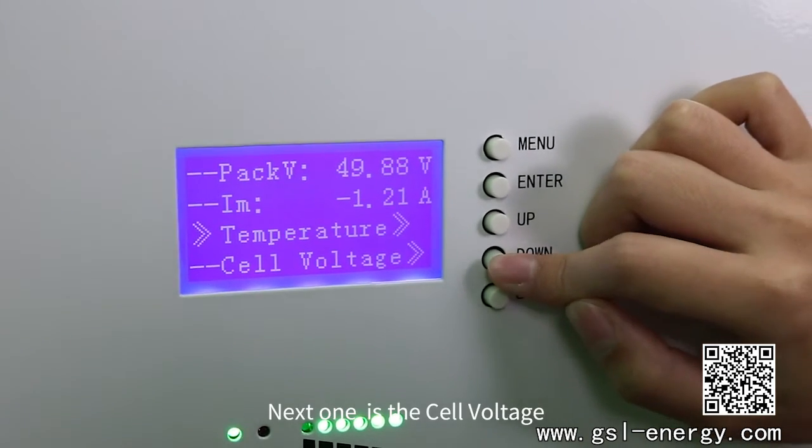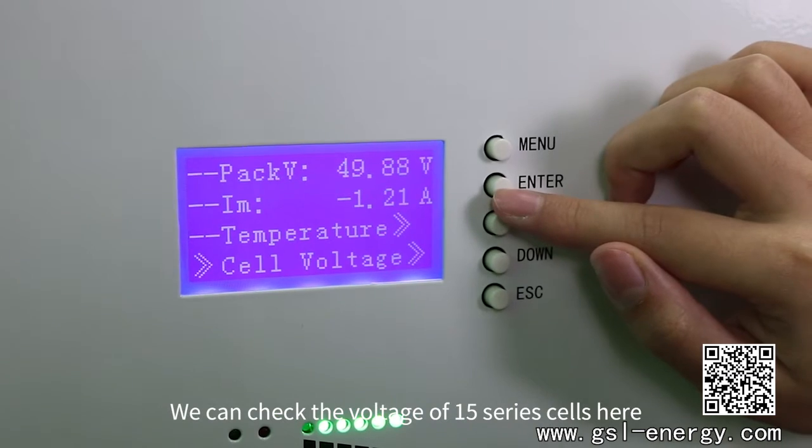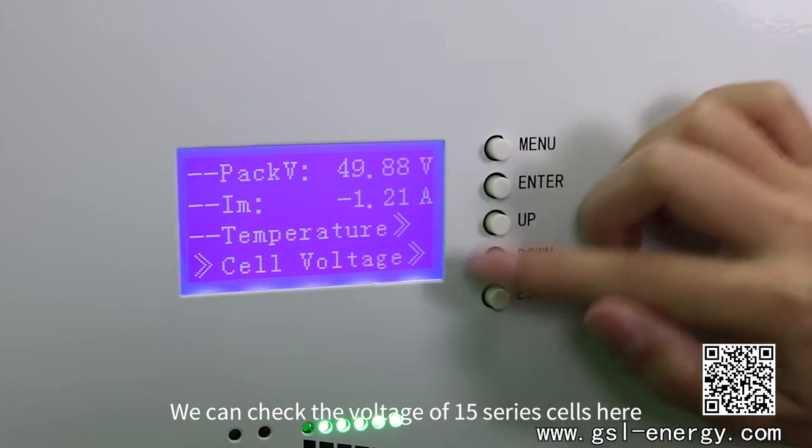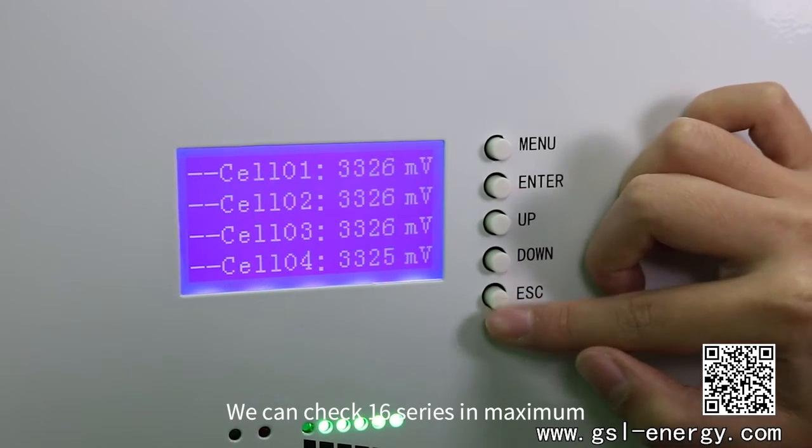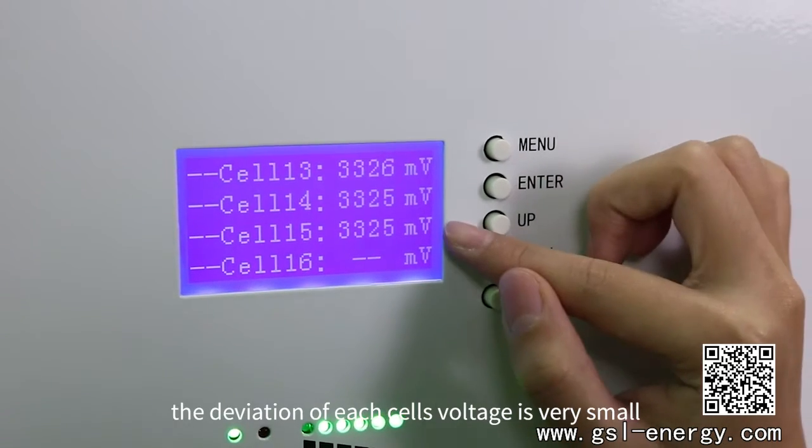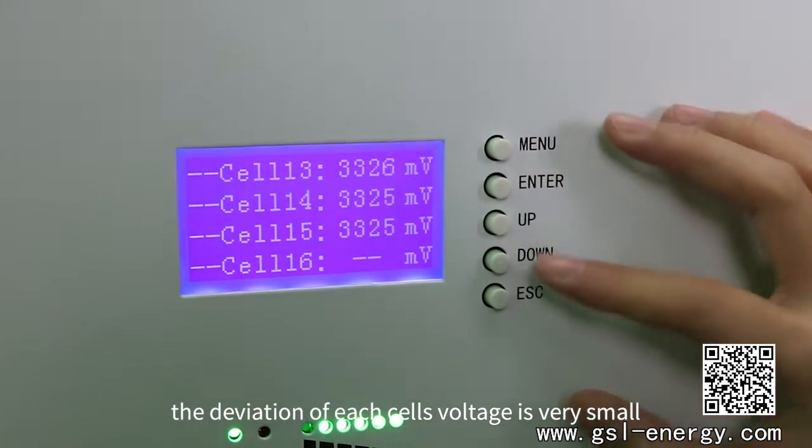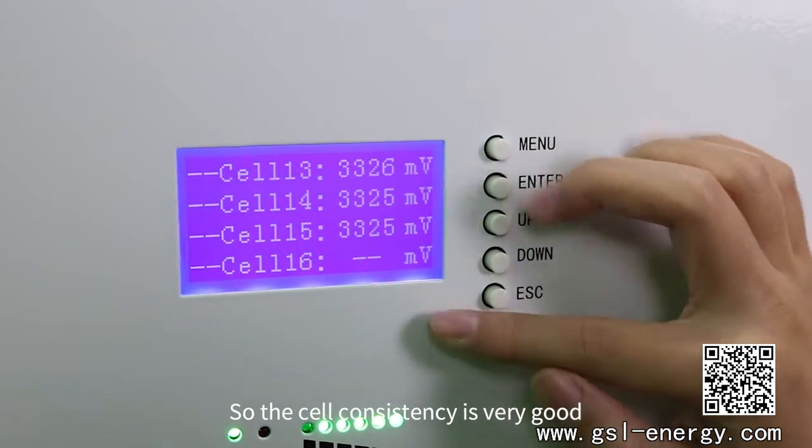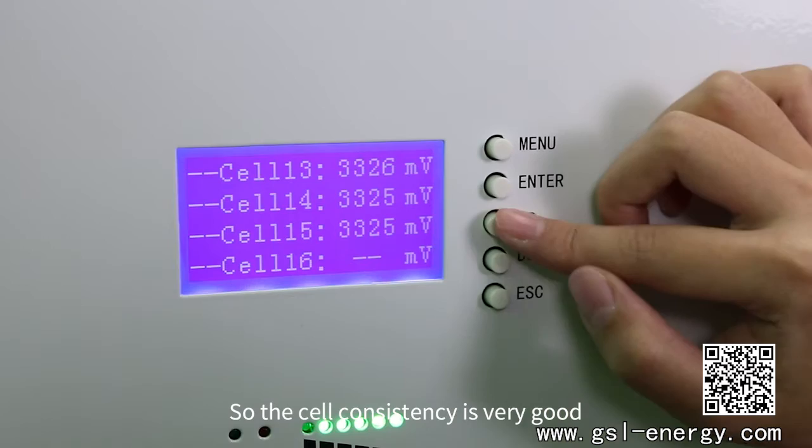Next one is the cell voltage. We can check the voltage of 15 series cells here. We can check 16 series in maximum. Also, we can see the deviation of each cell's voltage is very small, so the cell consistency is very good.